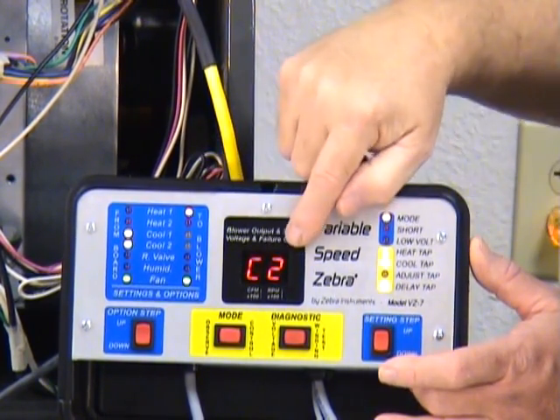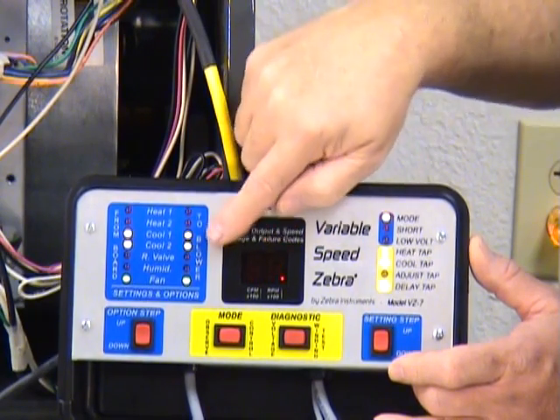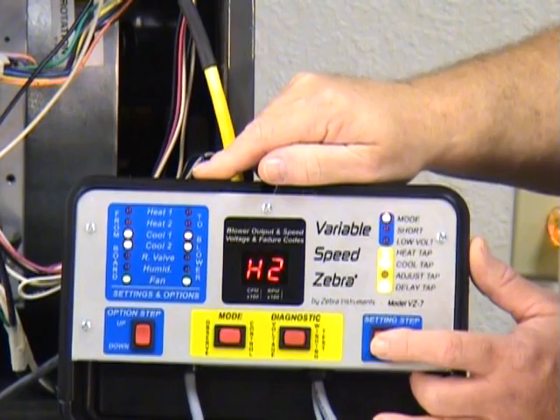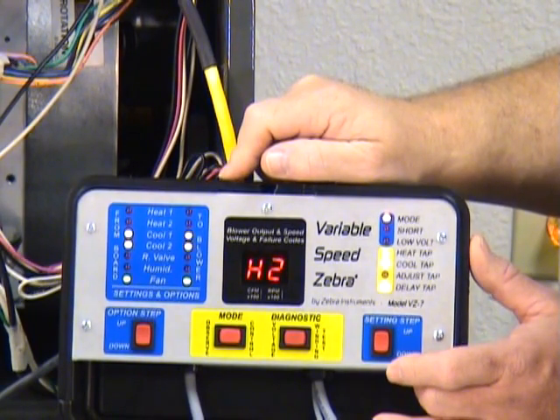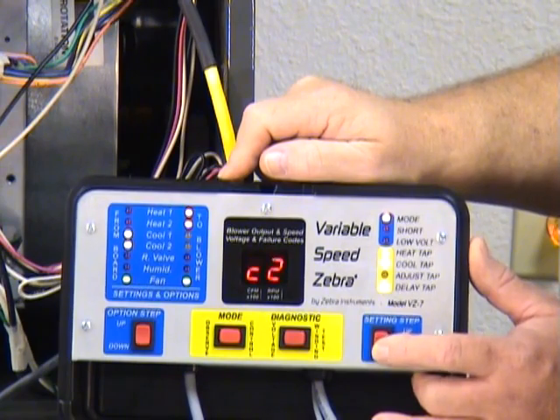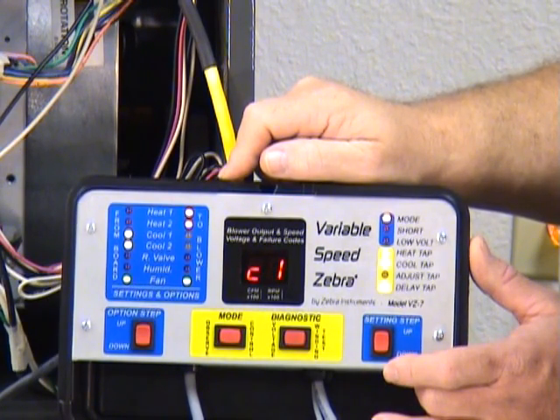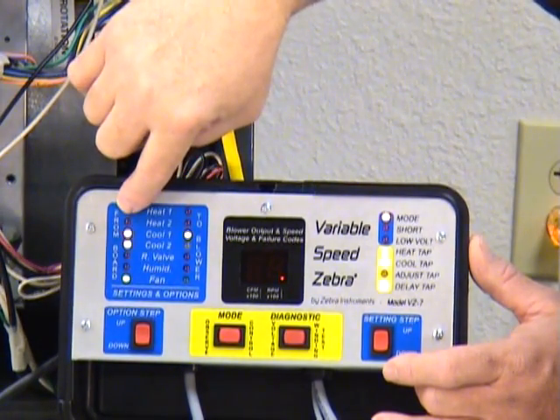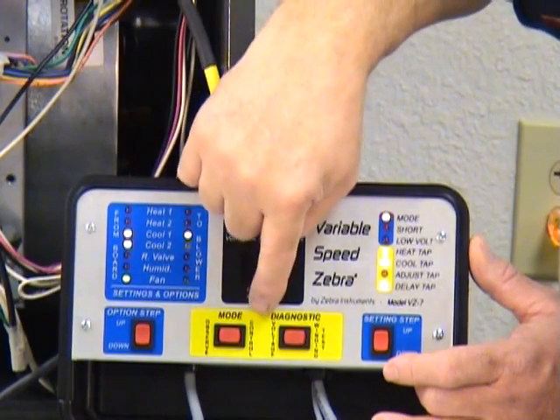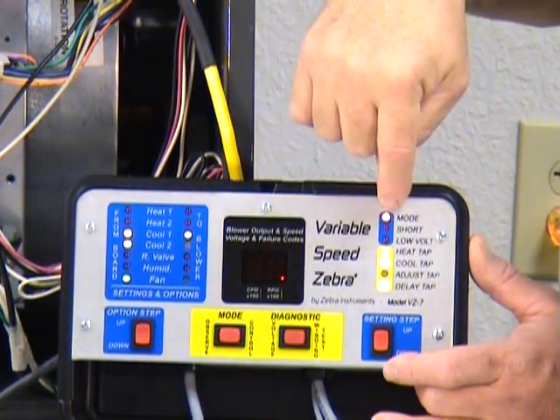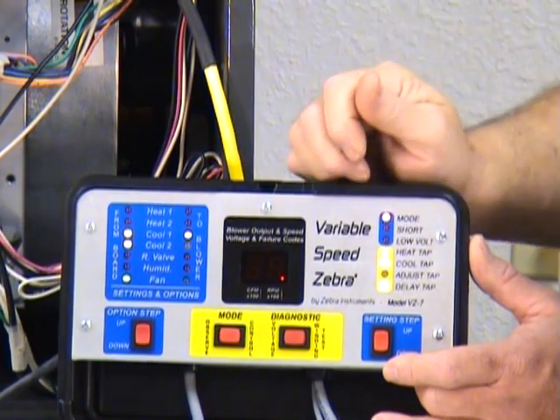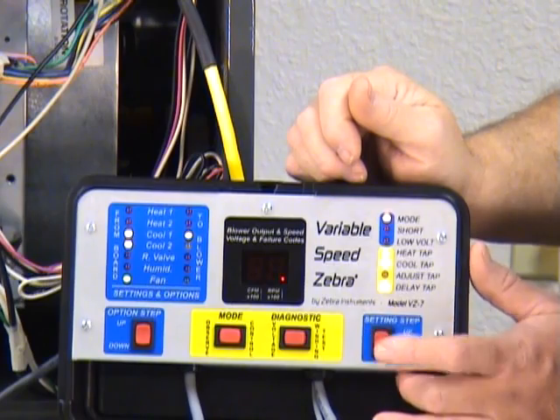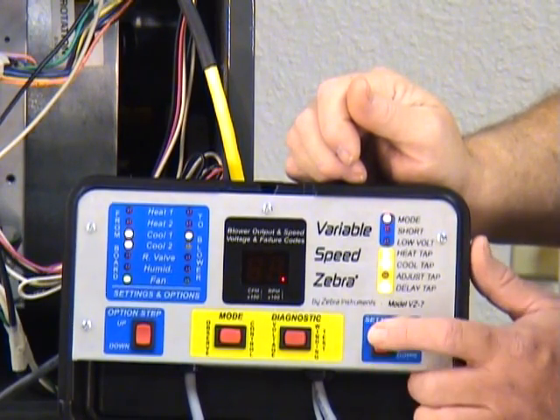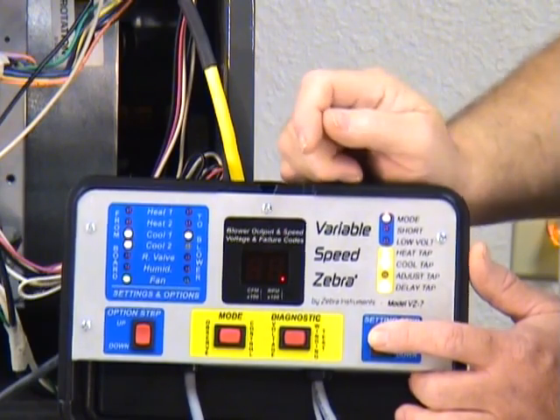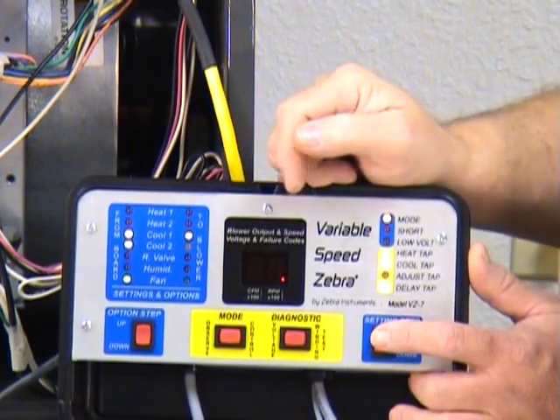We're going to run high-speed cooling with fan now because it's a capital C. Okay? We're going to run high-speed heating with a capital H with fan. And to demonstrate low-speed cooling without a fan, should be just one yellow light. Okay? Again, these lights have no effect on what the motor does when you're in control mode, red light mode. Red light means you're controlling it, green mode means you're simply watching it. So that is your setting step switch. These change the major thermostatic calls going to your motor: heat, cool, and fan.